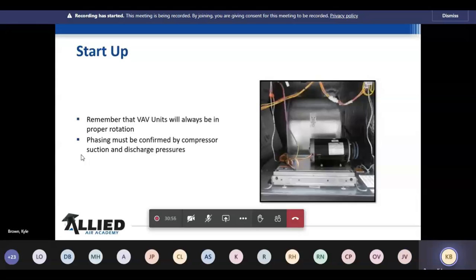So if you have those drives in there, and we use Mitsubishi, but again, we'll talk about the drives next week, they're going to correct it. They've got an auto correction in there for that. You still need to check it. That doesn't mean you bypass this step. And I've heard a lot of technicians say, well, I've got that VFD down here and it should correct it, so I'm not going to worry about it. No, go ahead and make the check. And we're going to confirm that by suction and discharge pressures, but startup sheets are going to help with that as well. So that's the blower section.